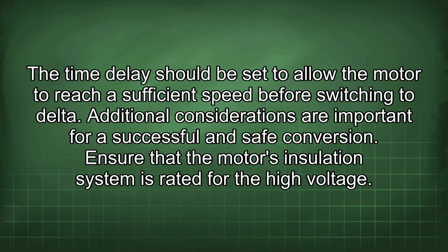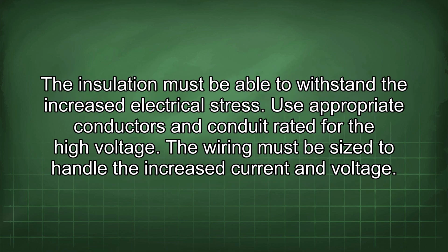Additional considerations are important for a successful and safe conversion. Ensure that the motor's insulation system is rated for the high voltage. The insulation must be able to withstand the increased electrical stress. Use appropriate conductors and conduit rated for the high voltage. The wiring must be sized to handle the increased current and voltage.